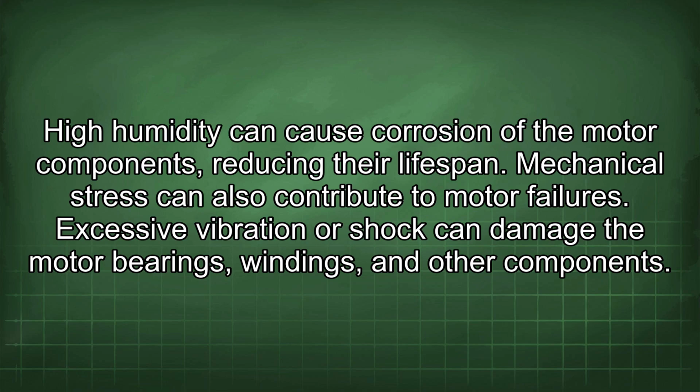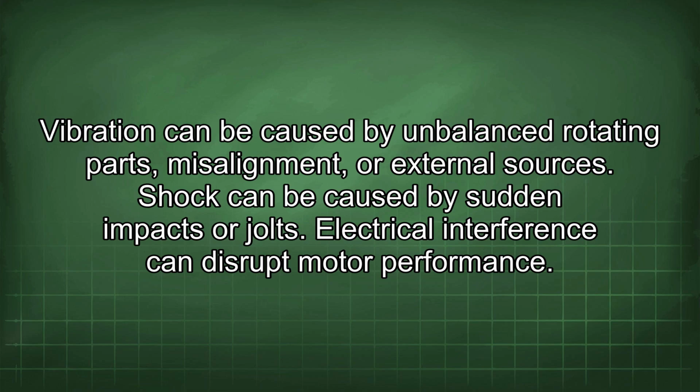Mechanical stress can also contribute to motor failures. Excessive vibration or shock can damage the motor bearings, windings, and other components. Vibration can be caused by unbalanced rotating parts, misalignment, or external sources. Shock can be caused by sudden impacts or jolts.